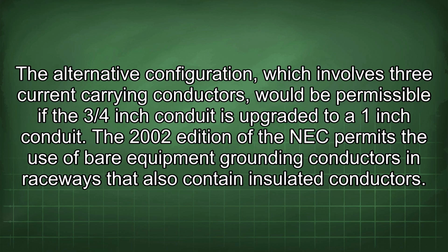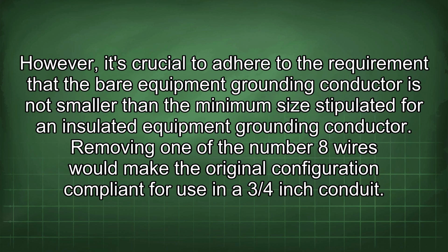The 2002 edition of the NEC permits the use of bare equipment grounding conductors in raceways that also contain insulated conductors. However, it's crucial to adhere to the requirement that the bare equipment grounding conductor is not smaller than the minimum size stipulated for an insulated equipment grounding conductor.